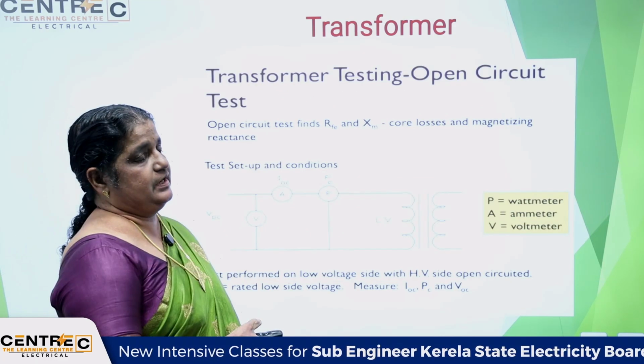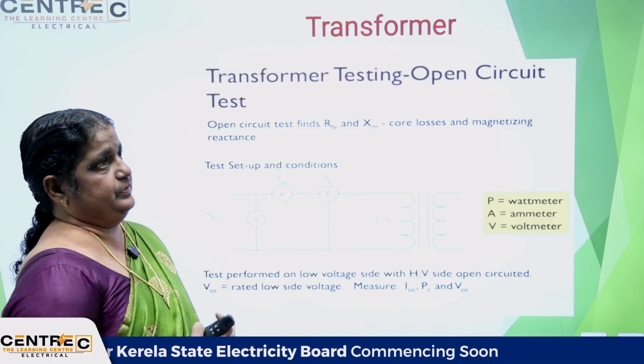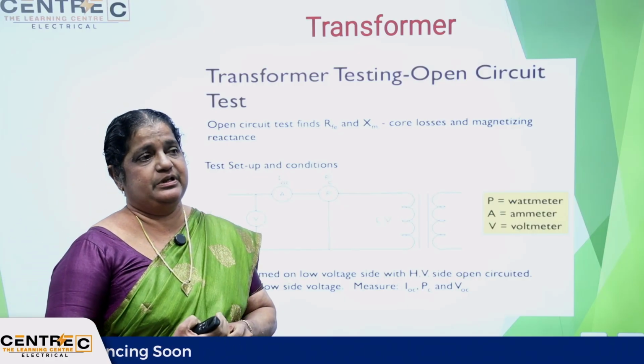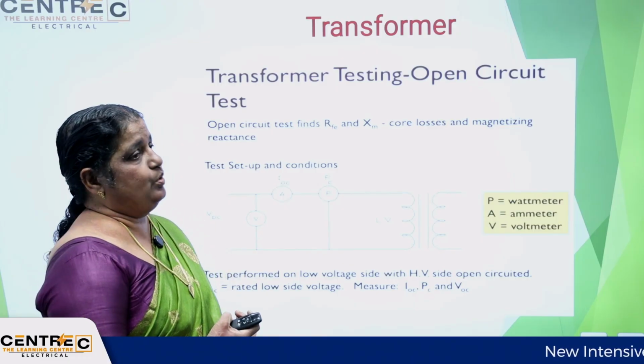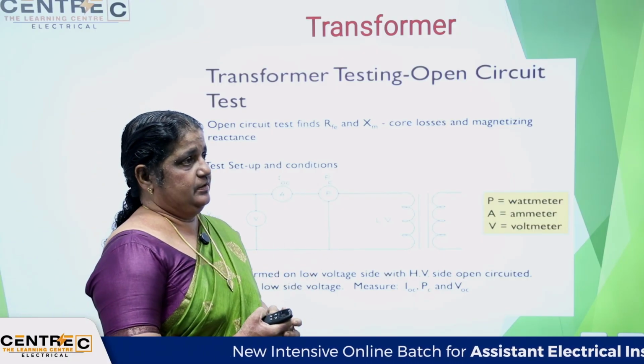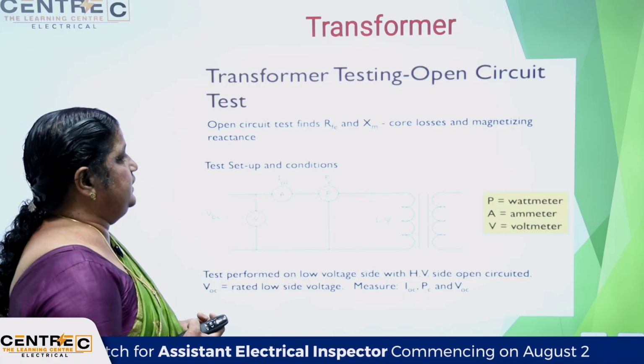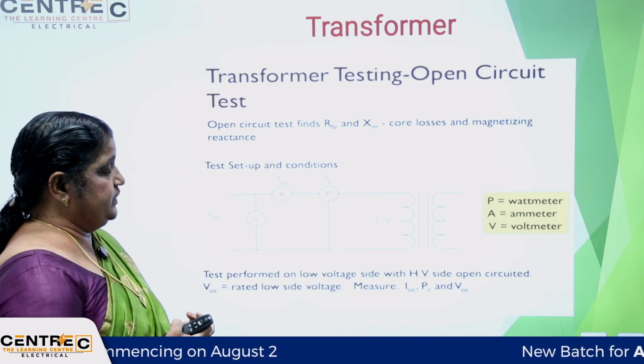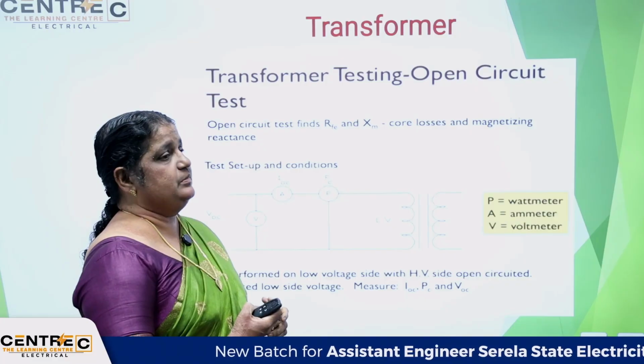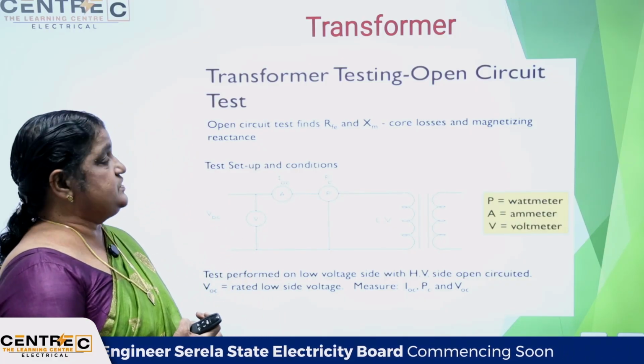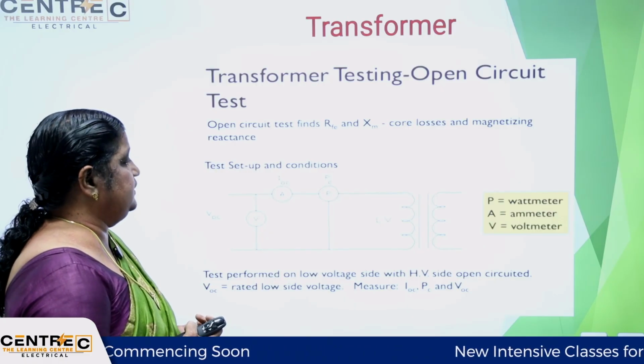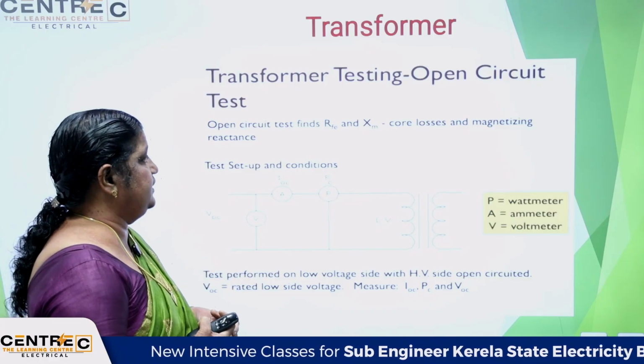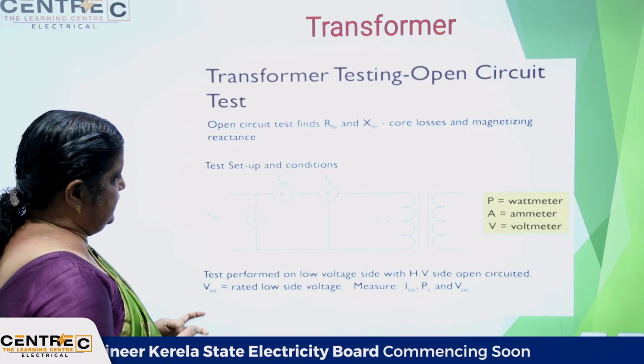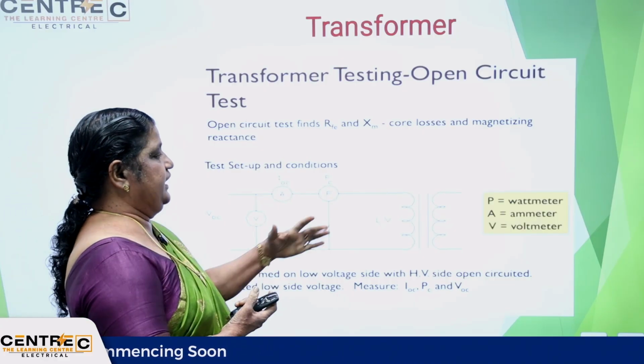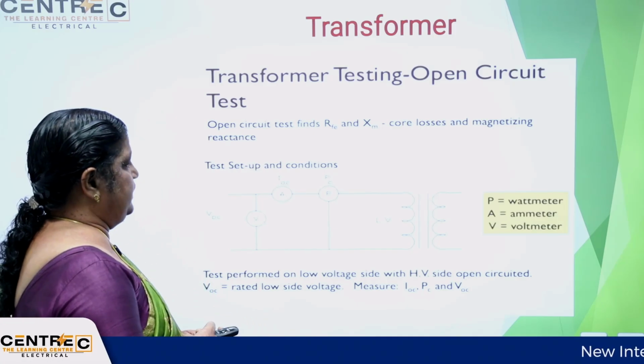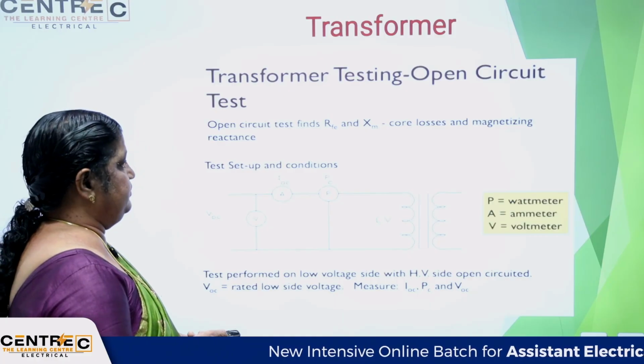Then for testing of the transformer, before giving the transformer to a consumer, the manufacturers provide important information about the transformer, such as its loss, efficiency and other things. To predetermine the efficiency, losses and other things, we use testing of the transformer. First is the open circuit test and then the short circuit test. From these test results, we can predetermine all the performance values of the transformer. The open circuit test is used to find the core loss of the transformer. In the circuit, the secondary is open circuited and rated voltage is applied to the primary. The wattmeter reading gives the core loss of the transformer.